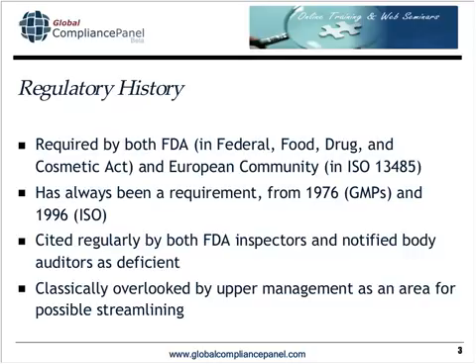It was recognized very, very early that one of the most critical aspects of the manufacture of medical devices is repeatability. This was not just recognized by the drafters of the standards, but also by the companies themselves. All medical device companies that I know of that were in business prior to 1976, which for those of you who weren't around then, was when the FDA first promulgated their good manufacturing practice regulations, in which document control was part. All of those had some kind of document control system in place.